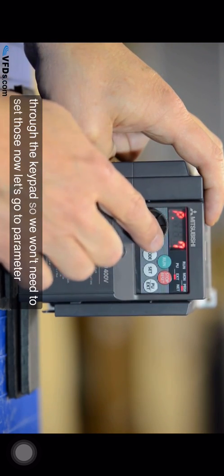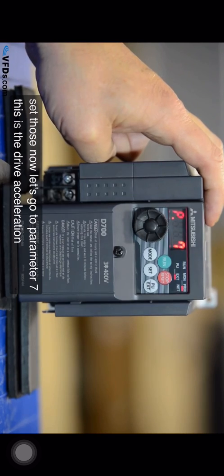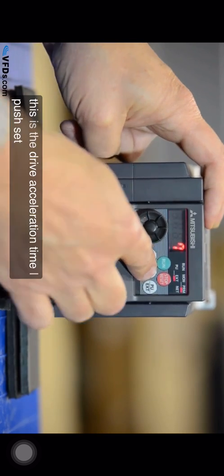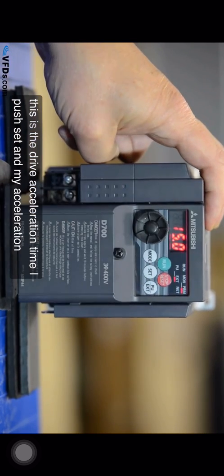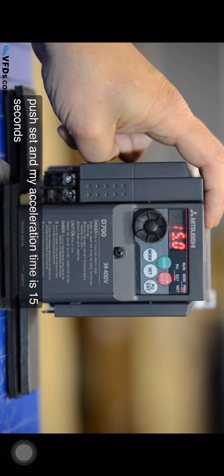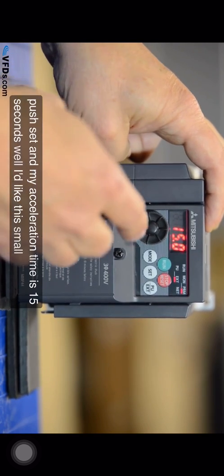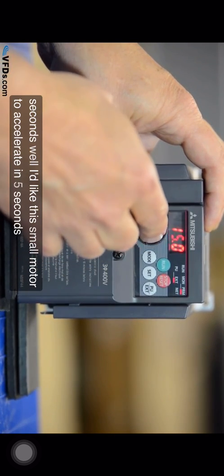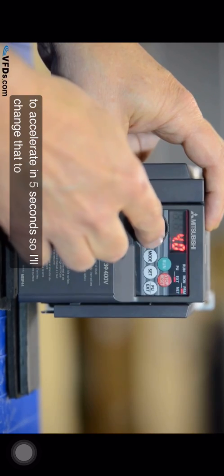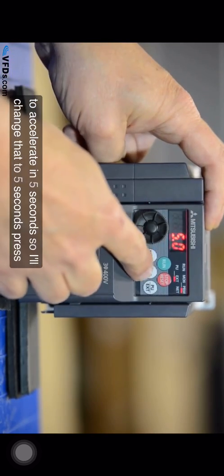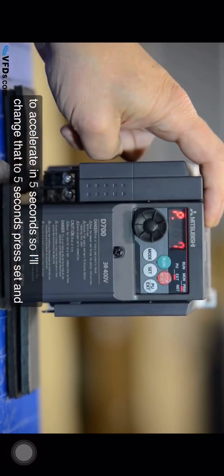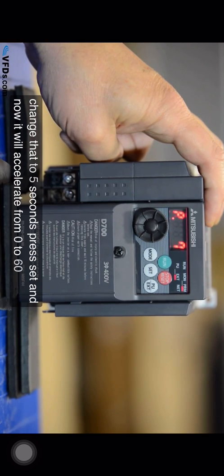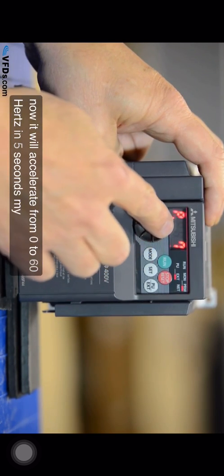Now let's go to parameter seven. This is the drive acceleration time. I push set and my acceleration time is 15 seconds. Well I'd like this small motor to accelerate in five seconds so I'll change that to five seconds. Press set and now it will accelerate from zero to 60 hertz in five seconds.